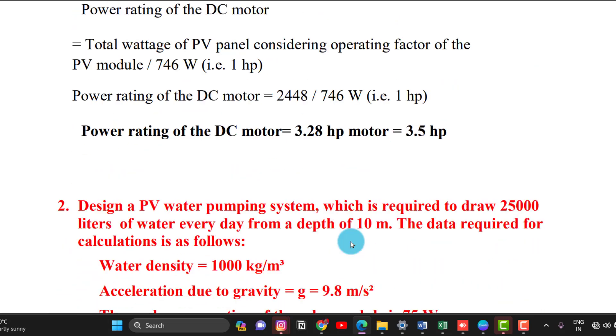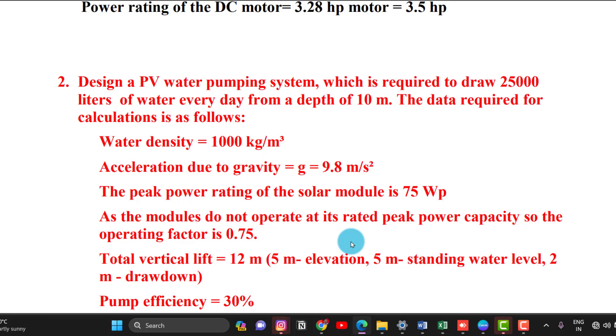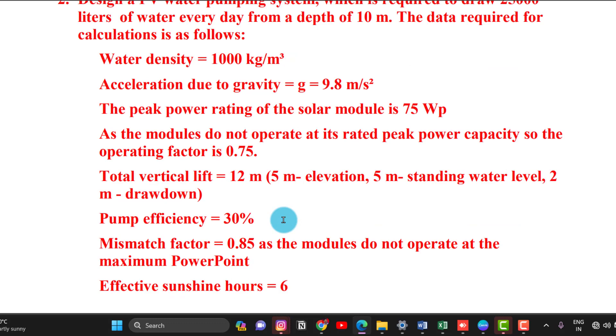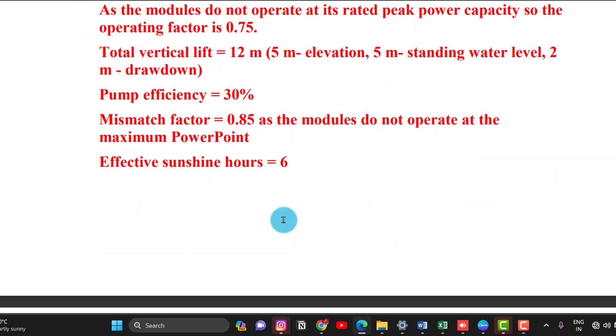The next example: design a PV water pumping system required to pump 25,000 litres of water every day from a depth of 10 meters. Given data: water density 1000 kg/m³, gravity 9.8 m/s², solar panel peak power 75 Watt peak, operating factor 0.75, total vertical lift 12 meters (elevation 5 m, standing water level 5 m, drawdown 2 m), pump efficiency 30%, mismatch factor 0.85, and peak sunshine 6 hours per day.